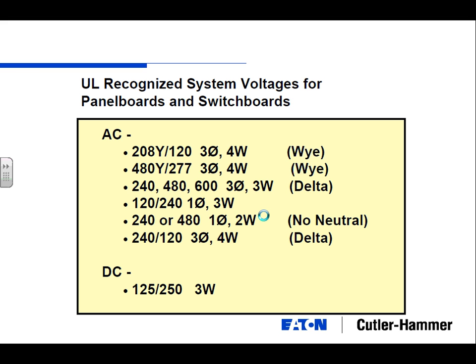So these are the voltages that we have to follow. 208/120Y is very common, as well as 480Y/277. Those are two of the most common voltages you're going to see that come into a facility for power distribution. Those same voltages in the delta formation are also available. You'll see those more in an industrial type application where you don't necessarily need a neutral, or you have more three-phase loads than single-phase loads.